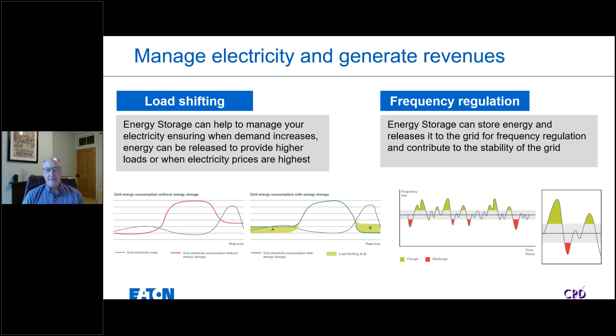We spoke about frequency regulation in quite some depth earlier, so I won't go into too much detail here, but this is just illustrating how the storage system can monitor the grid frequency and then automatically charge when the frequency is increasing. So we effectively add a load to the system to take some energy off and help manage that increase in frequency, and discharge when the frequency drops. So we support that imbalance between demand and supply on the system.